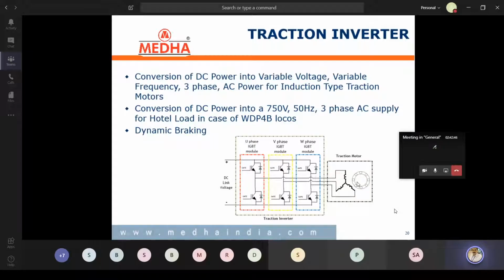It acts as a generator and most of the time it will generate its output. For some time it will take the input, and most of the time current will come out from the motor. So this three phase AC comes to this inverter and here these diodes act as a full wave bridge rectifier, and the three phase AC converts back into DC, and this DC goes to those grid resistors by energizing the DC link contactors, that is, the brake chopper contactor or these normal contactors for braking purpose, B1, B2, B3, B4. Accordingly, we'll get the braking effort.